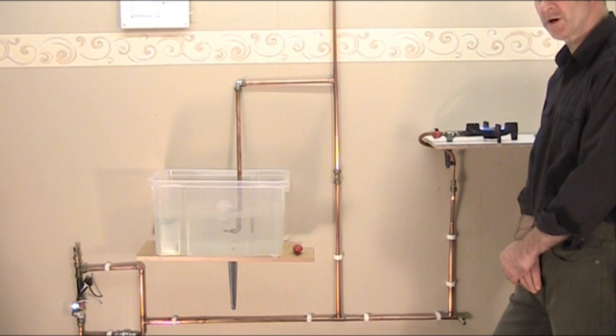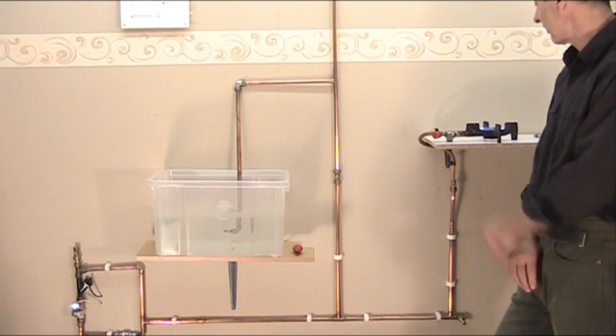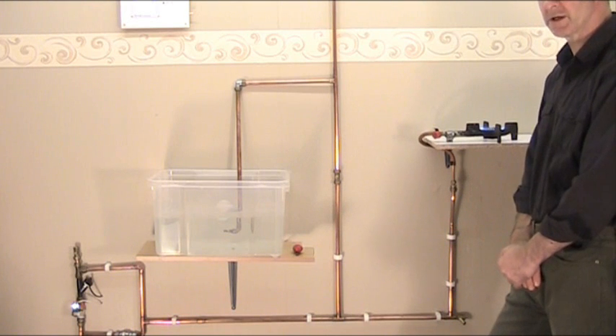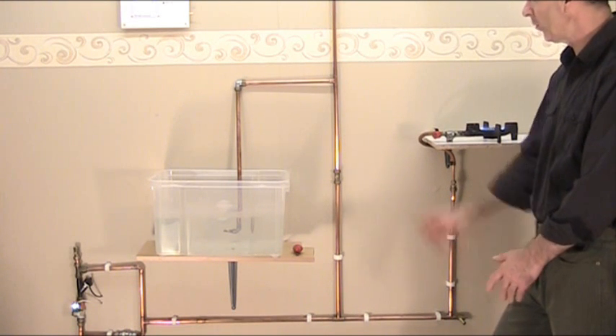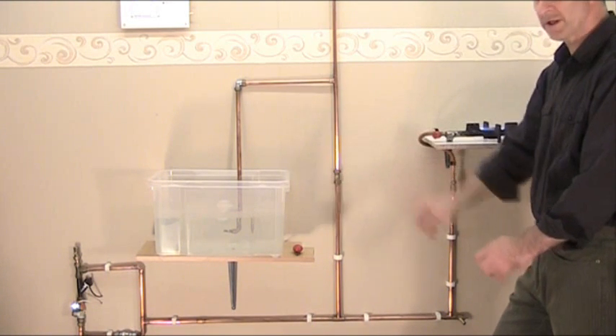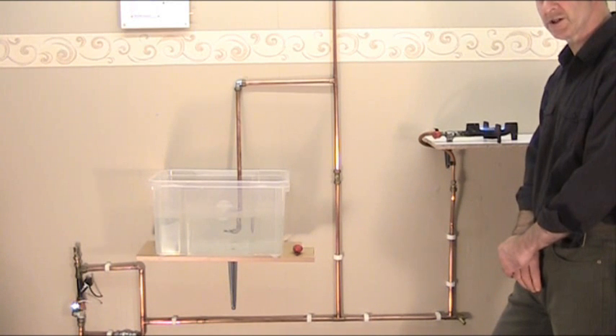The Burst Off is now armed in the protecting state, and as you can see, the gas is still running, flowing through the pipes as normal. I'm going to open that valve again and let the gas come through to the open end in the pipe there, which will simulate a burst or leak in your system. I'll open it now.